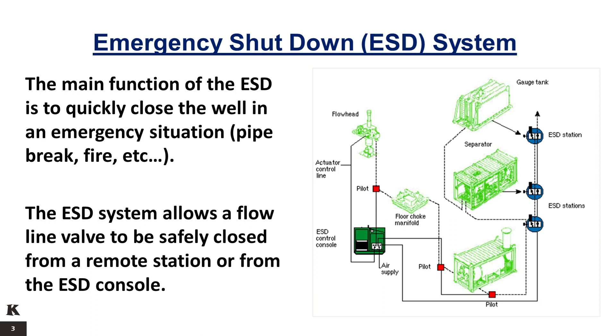The equipment consists of a pneumatic console which pressurizes the various pneumatic and hydraulic circuits, push-pull shutdown stations, and in some instances, high-low pressure pilots. In an emergency, either the pressure pilots or the manual ESD stations release the air pressure in the system. The hydraulic circuit is then bled off by the interface valve in the console and the fail-safe valve closes.